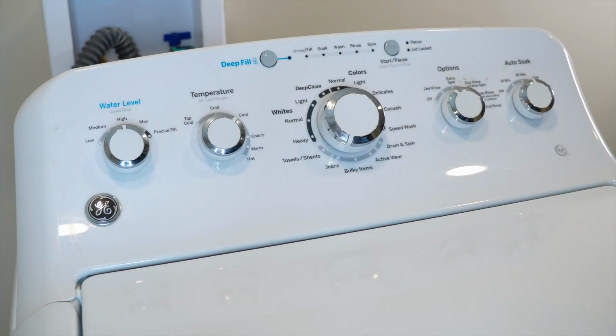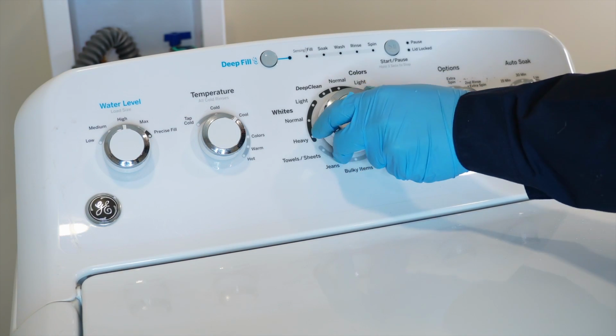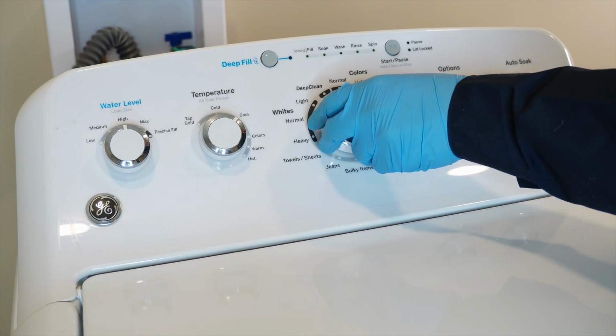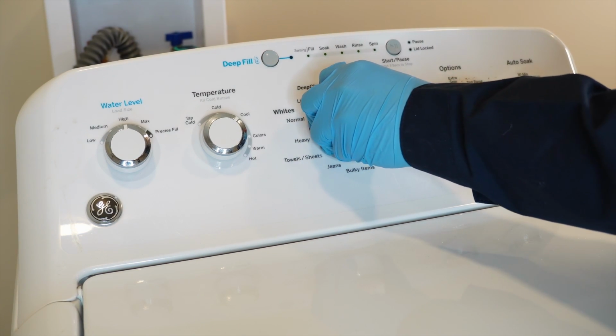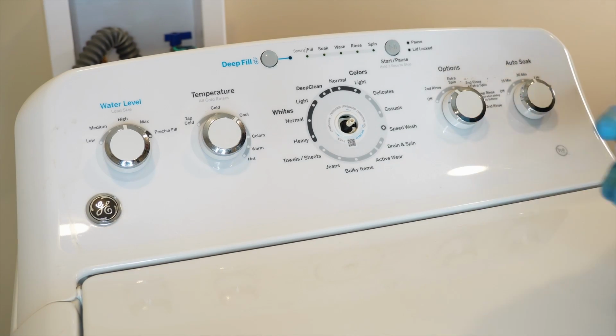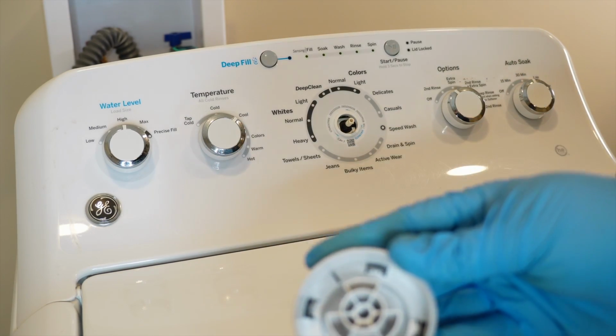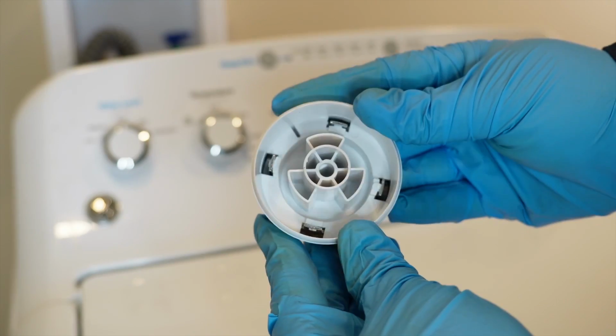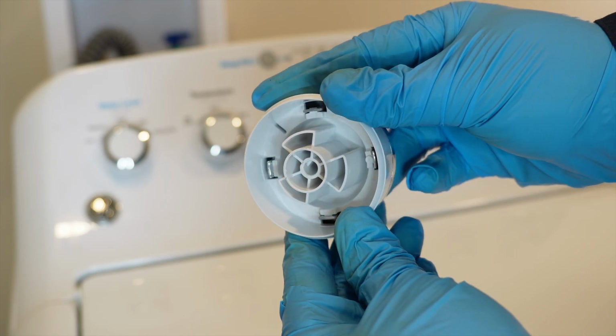Possibly the first most basic thing, turn the dial. Does the machine make a noise? In some instances, the inside of the dial could be cracked or damaged, and it won't let you select a valid mode. Also, make sure to press the start button and make sure that the unit makes a clicking sound.